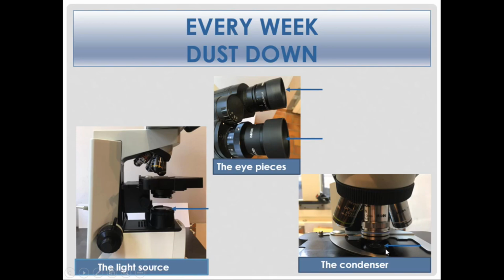If dust accumulates in either of these two areas, then your light source will be less bright and the quality of your images less good. And then the eyepieces here. Dust will collect in these, and sometimes infectious conjunctivitis can be transmitted from eyepieces, so giving them a good clean with alcohol from time to time is highly recommended.